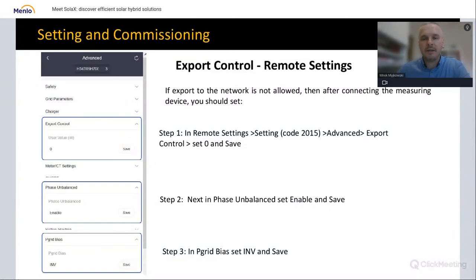There can always be a little bit of power going into the grid, but to make this as small as possible, so as close to zero as possible, we strongly recommend not only setting export control to zero, but also enabling unbalanced phase, and setting Pgrid bias to inverter.